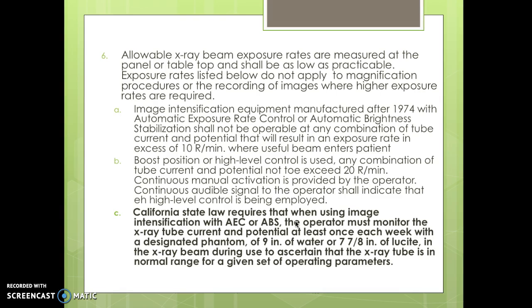Boost mode, or high level control, is used when any combination of tube current and potential must not exceed 20 R per minute. Continuous manual activation is provided by the operator, and a continuous audible signal shall indicate that the high level control is being employed. The State of California requires that when using image intensification with ABC or ABS, the operator must monitor the x-ray tube current and potential at least once a week with a designated phantom of nine inches of water or seven and seven-eighths inches of Lucite in the x-ray beam, to ascertain that the x-ray tube is within normal range for its given operating parameters.